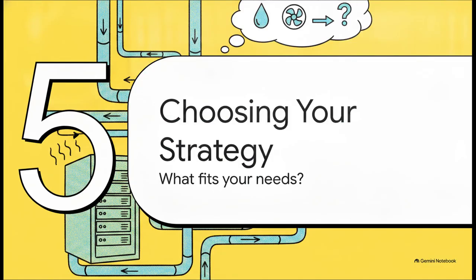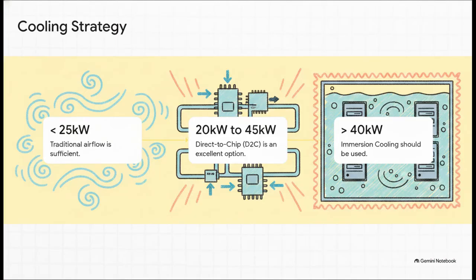And that brings us to our final section, number 5, choosing your cooling strategy. The source material lays out this brilliantly simple rule of thumb progression based on your total heat load per rack. Step 1, if your rack is only generating up to 25 kilowatts of heat, traditional airflow is probably still sufficient for now. Step 2, once you cross into that 20 to 45 kilowatt zone, direct-to-chip becomes an excellent, highly efficient option. But step 3, if you're pushing above 40 kilowatts per rack or operating in a highly confined space, immersion cooling really transitions from being an option to being practically required.